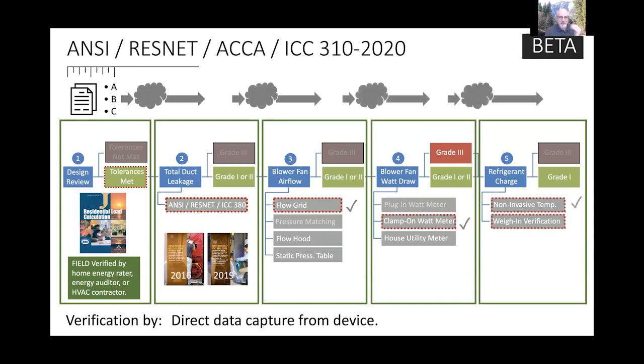And notice at the top, we're saving this stuff to the cloud. One person may go out and do a duct leakage test, then somebody else may come out and do the blower fan and airflow using the TrueFlow grid. Other options are out there, but in general the TrueFlow grid is an easily documented direct capture method. A clamp-on watt meter is your next one for the watt draw.